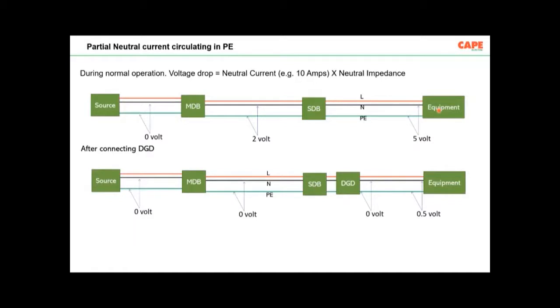In that condition, what people do, there are a lot of spurious or non-standard products available in the market. One such product is called a digital grounding device. The manufacturer will claim so many parameters. Whatever problems you have, he will call this device a digital grounding device, which I have put as DGD. All solutions are available in this particular device. Practically what they do is they simply connect neutral and earth.